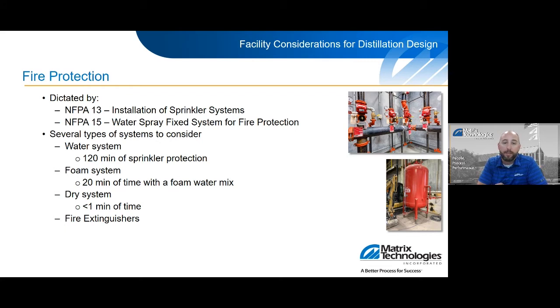Second type of system that I've seen quite a bit in the spirits world is a foam water mix. So this does take a tank, kind of the lower picture there, that mixes with the fire water and puts out the fire that way. The advantage of this system is demand goes from 120 minutes down to 20 minutes, which drastically reduces the volume or the demand on your system, and also minimizes how much you need to contain.